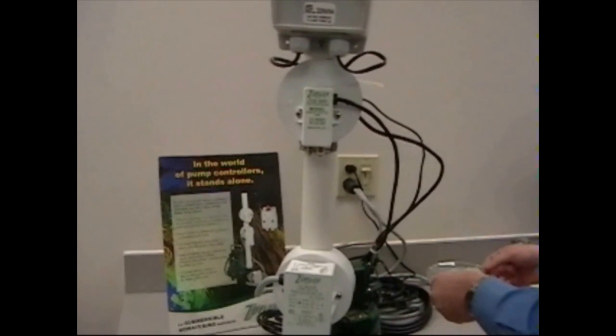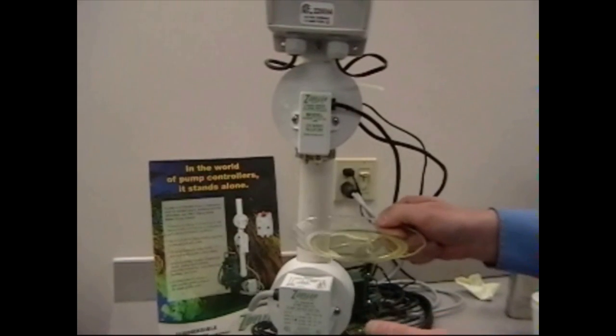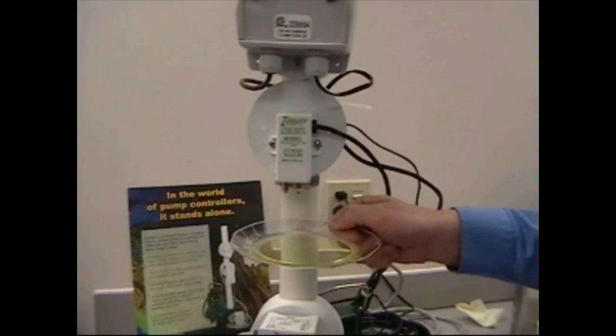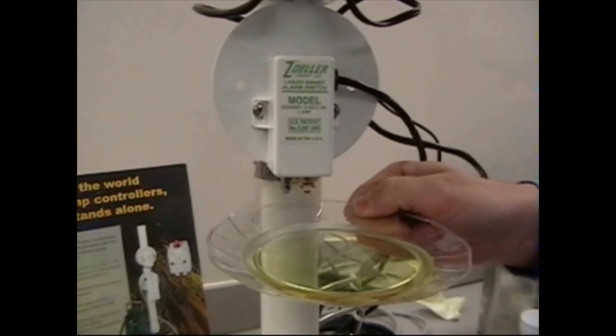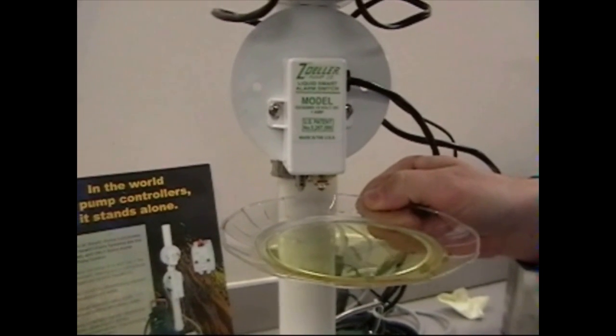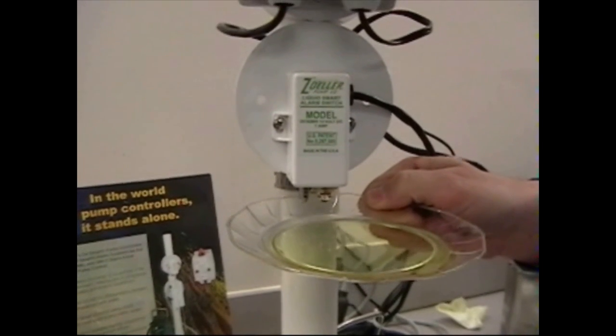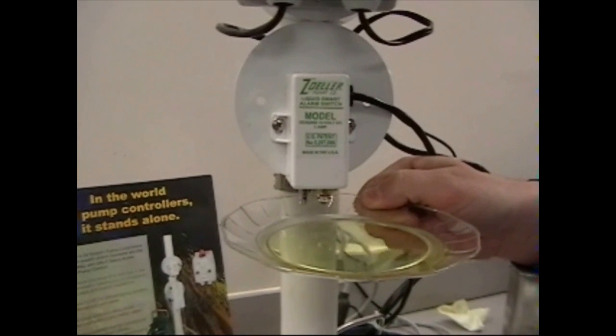If there was an excessive amount of oil in the pit, if you can imagine, over time this pump is pumping, working as it should, and more and more oil is accumulating in the pit because of a leaking issue or some type of condition. Eventually so much oil will gather in that pit that the pump will no longer function.